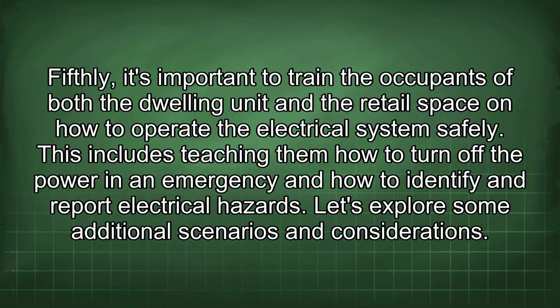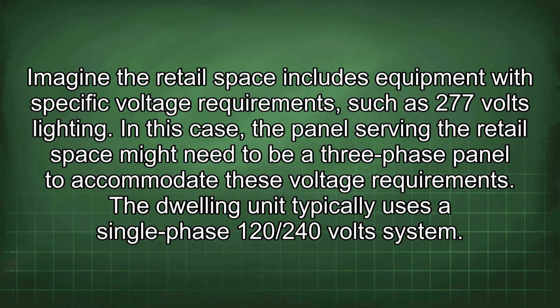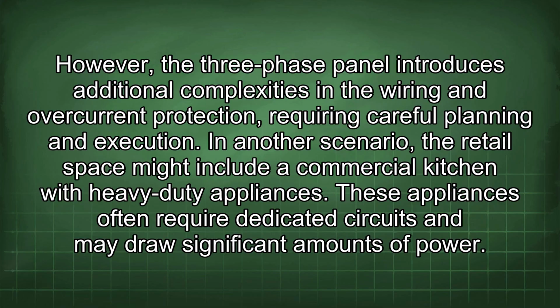Let's explore some additional scenarios and considerations. Imagine the retail space includes equipment with specific voltage requirements, such as 277 volts lighting. In this case, the panel serving the retail space might need to be a three-phase panel to accommodate these voltage requirements. The dwelling unit typically uses a single-phase 120/240 volt system. However, the three-phase panel introduces additional complexities in the wiring and overcurrent protection, requiring careful planning and execution.